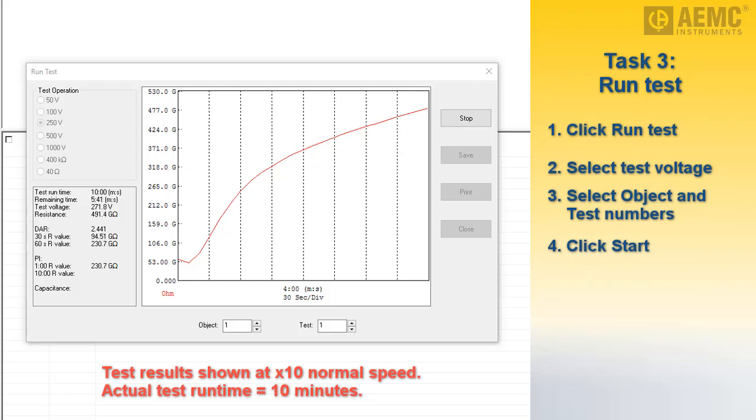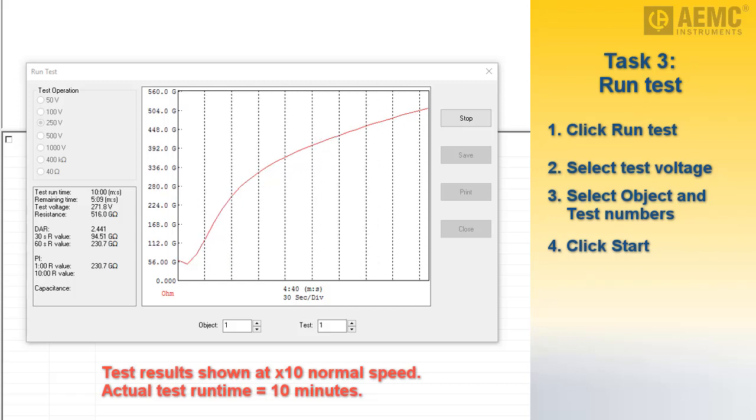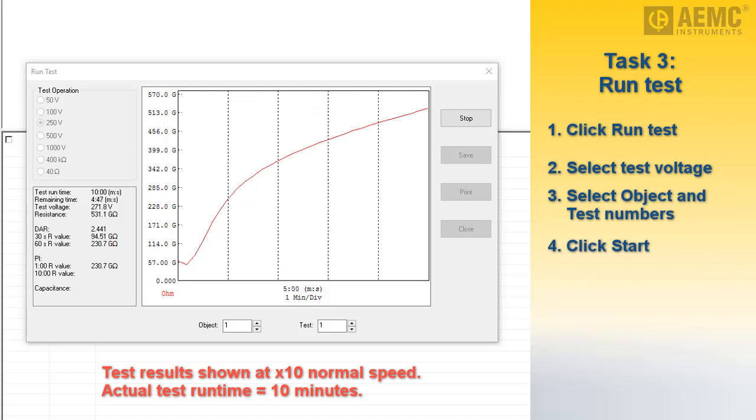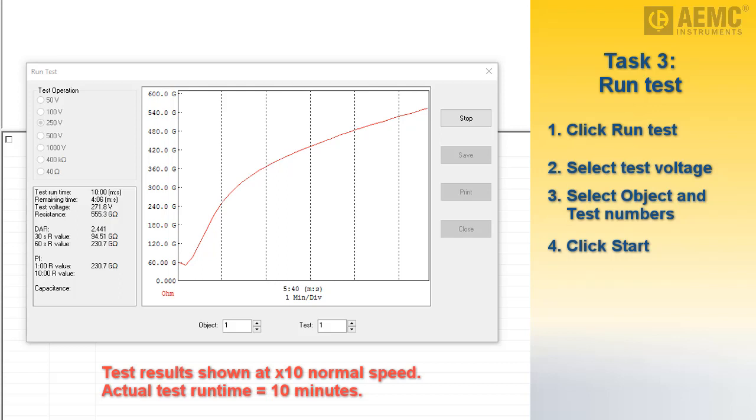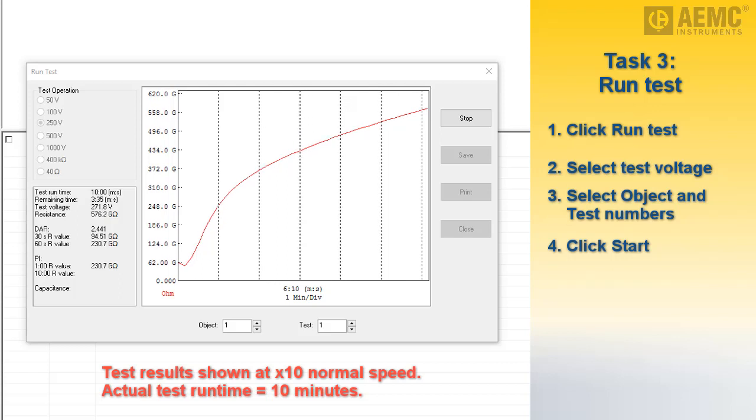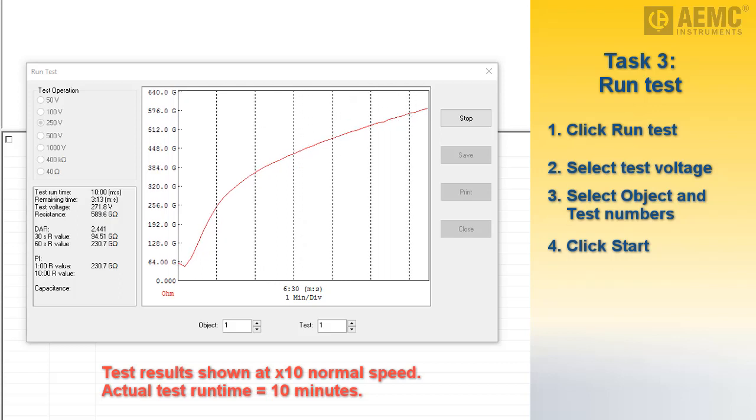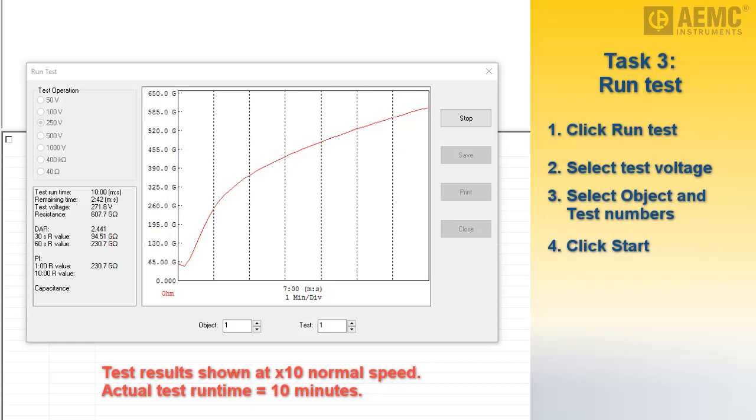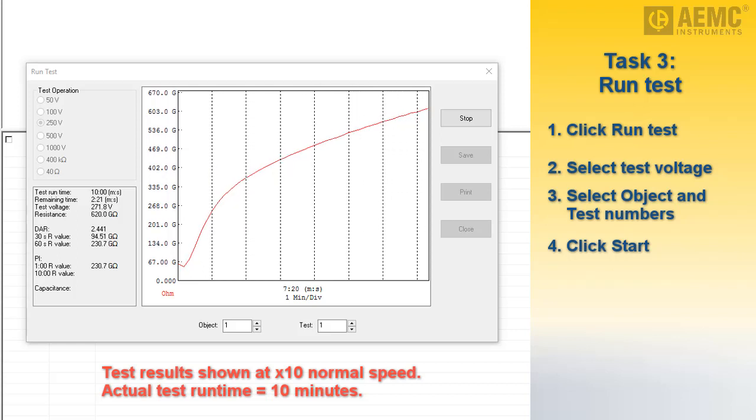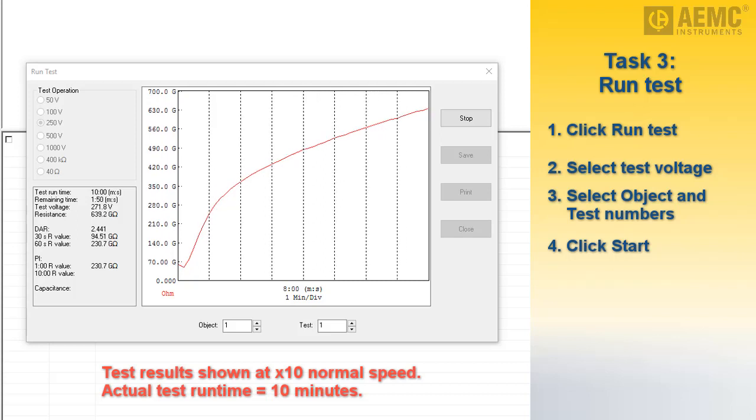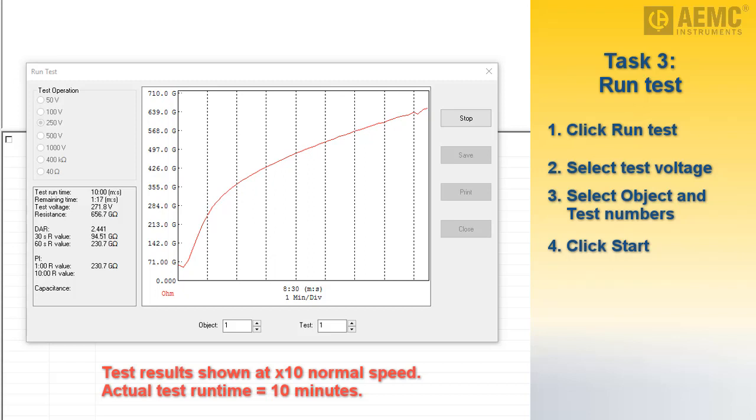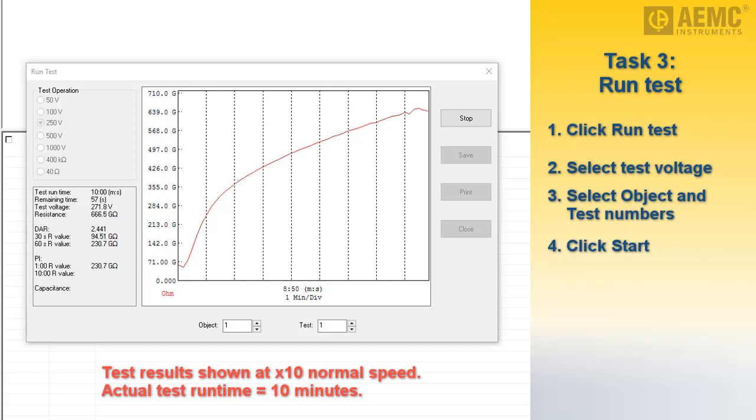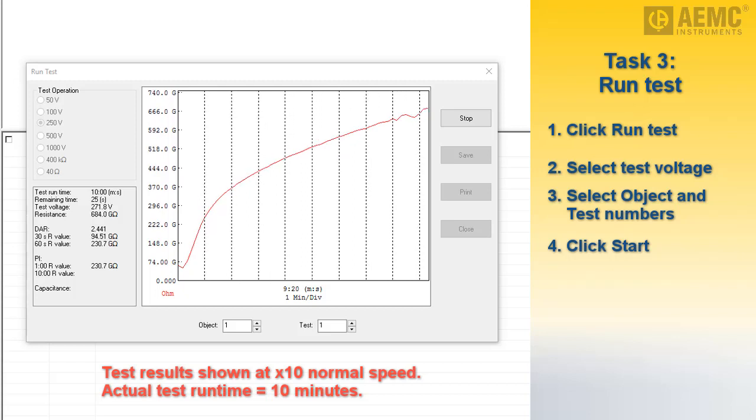As the test progresses, the graph starts to assume the characteristic shape of the time resistance test. In our demonstration, the graph indicates that our test specimen, in this case a short wiring run, has adequate insulation. It also indicates that we have selected an appropriate test voltage. If instead the graph quickly rises to the top of the display and measurements are listed as out of range, stop the test and run a second test at a higher test voltage.